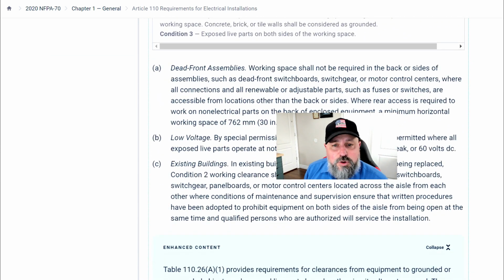A, dead front assemblies. Working space shall not be required in the back or sides of assemblies, such as dead front switchboards, switchgear, or motor control centers, where all connections and all renewable or adjustable parts, such as fuses or switches, are accessible from locations other than the back or sides. Where rear access is required to work on non-electrical parts on the back of the enclosed equipment, a minimum horizontal working space of 30 inches shall be provided. B, low voltage. By special permission, smaller working spaces shall be permitted where all exposed live parts operate at not greater than 30 volts, 42 volts, or 60 volts.